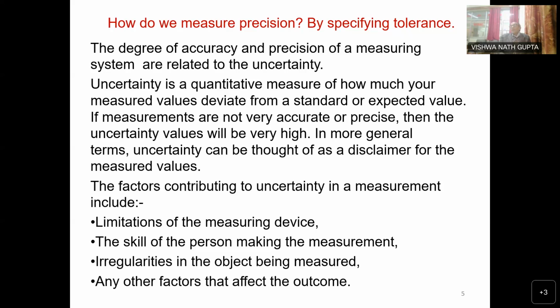In our testing industry too, if there is a limit as per IS standards, say high voltage should have not more than 3% uncertainty, then if uncertainty is more than 4% or 5%, even if we have a traceable calibration certificate, it is not going to solve our purpose.